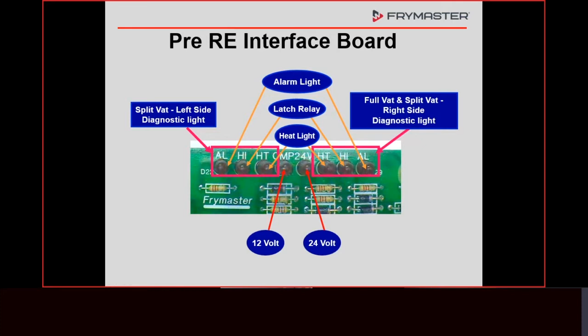If the latch relay is not closed when the fryer is on, that means there's a problem. I'll show you that when we get to the wiring diagram, but usually that means either our high limit or our drain switch is open, on fryers equipped with a drain switch. That's why it says HI, that stands for high limit, because it's in series with the high limit. This light or this light will always be on, one or the other. So if this light is off, this light will be on, as long as the fryer has power to it. This one is just going to come on whenever it calls for heat. That's what the lights mean.